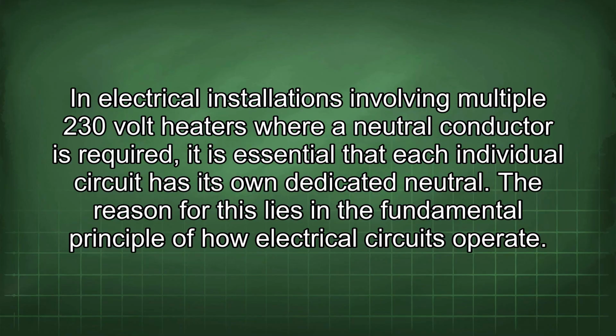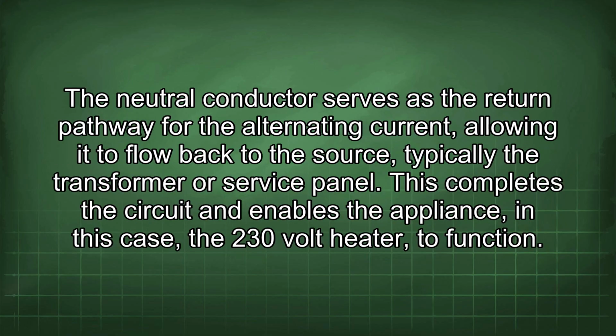In electrical installations involving multiple 230-volt heaters, where a neutral conductor is required, it is essential that each individual circuit has its own dedicated neutral. The reason for this lies in a fundamental principle of how electrical circuits operate. The neutral conductor serves as the return pathway for the alternating current, allowing it to flow back to the source, typically the transformer or service panel. This completes the circuit and enables the appliance, in this case the 230-volt heater, to function.